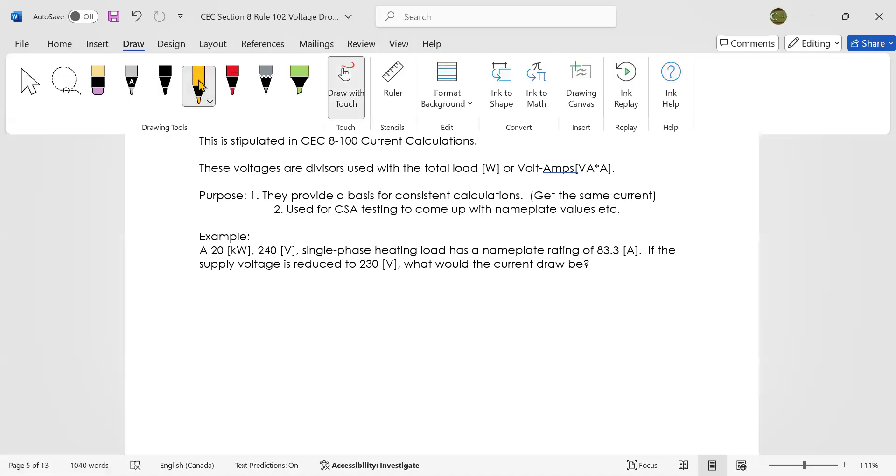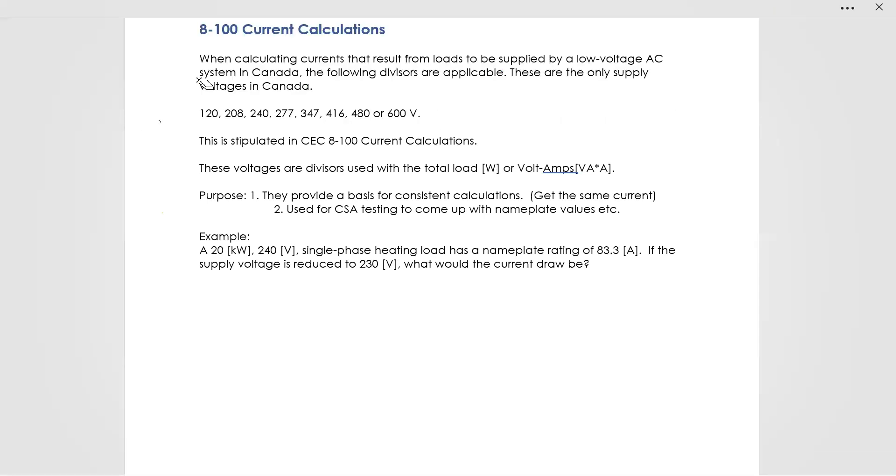So this rule says—let me read you the rule. When calculating currents that result from loads expressed in watts or volt-amps to be supplied by a low voltage AC system in Canada, the voltage divisors to be used shall be 120, 208, 240, 277, 347, 416, 480, or 600 volts as applicable. That's what the whole rule said.